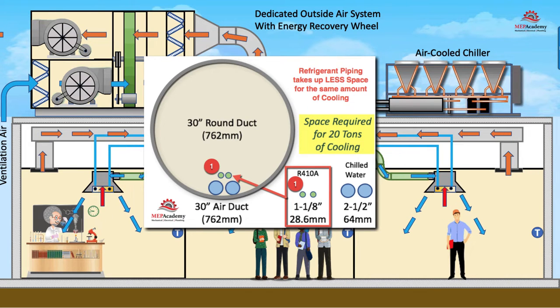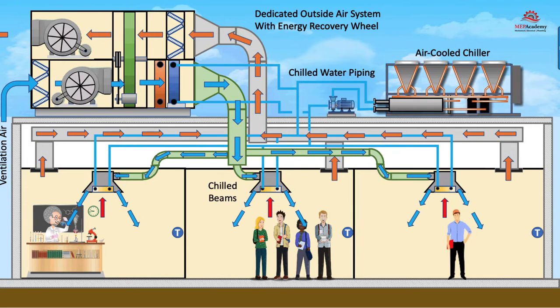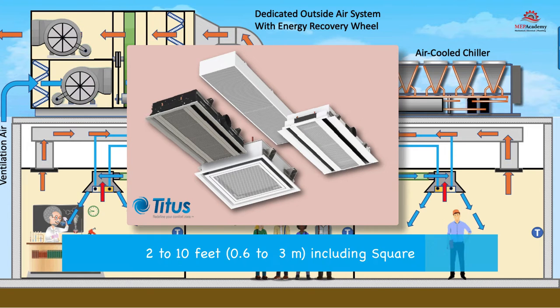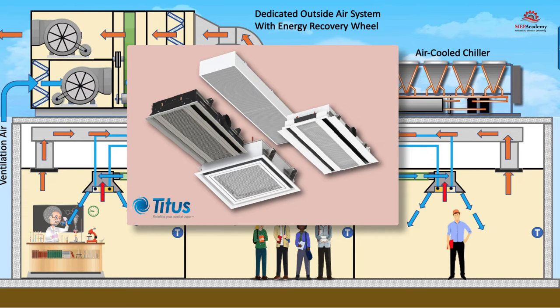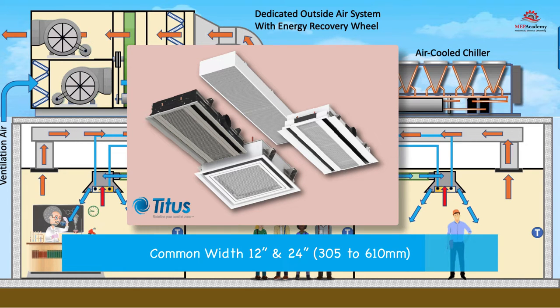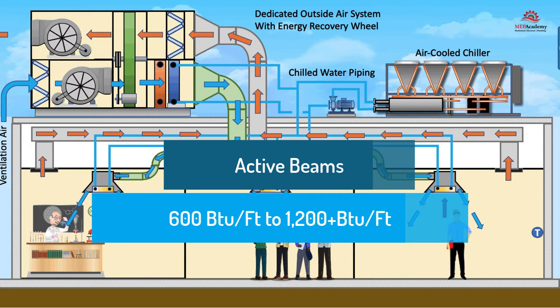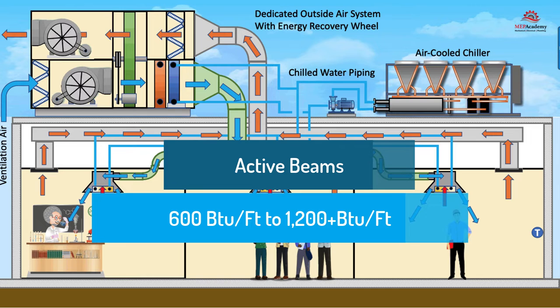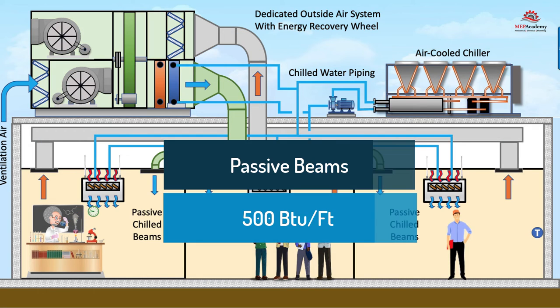With the use of chilled water at the zone level, large ductwork can be avoided. Active chilled beams come in lengths from 2 feet to 10 feet with various output values per manufacturer. Outputs range based on width of unit, with common widths of 12 inch and 24 inch. Cooling capacity of active beams can range from 600 BTUs per foot to 1,200 BTUs per foot based on make and model, while passive beams will have lower outputs in the range of 500 BTUs per foot.